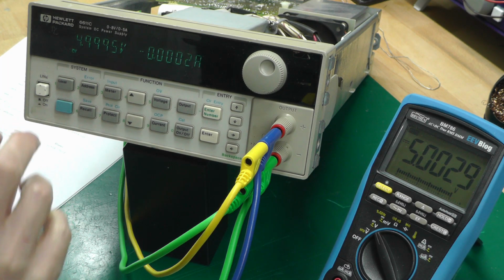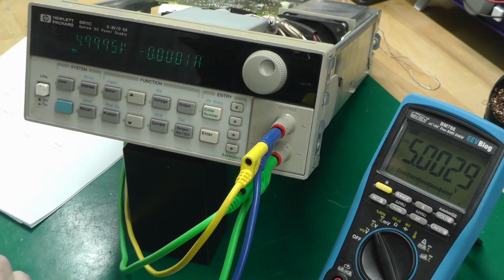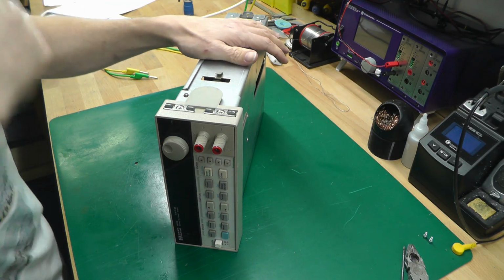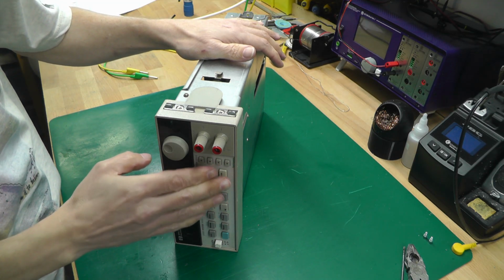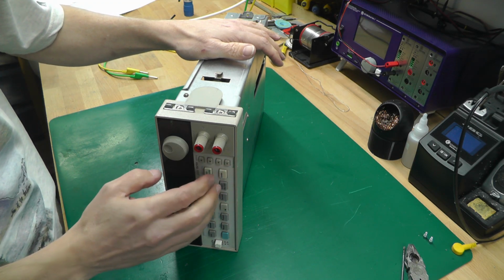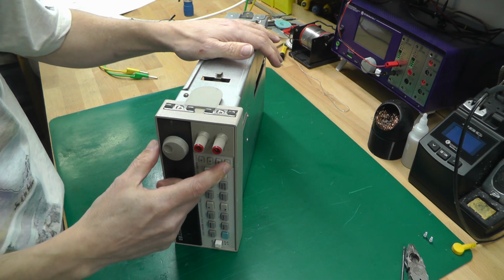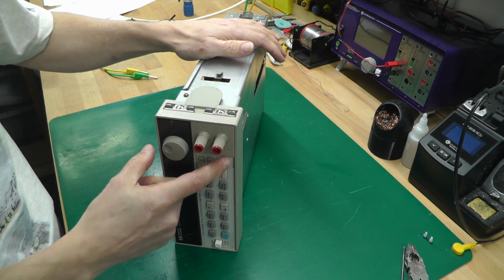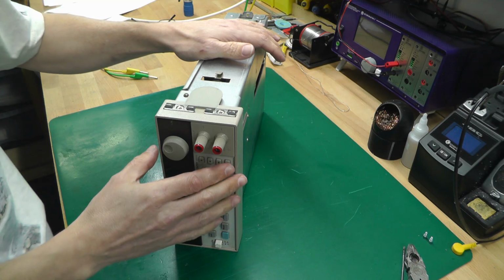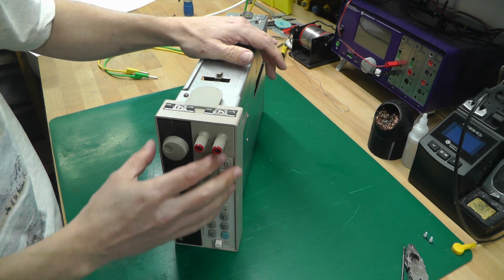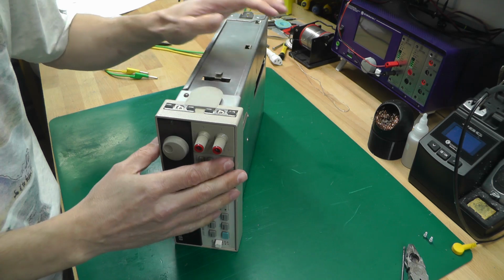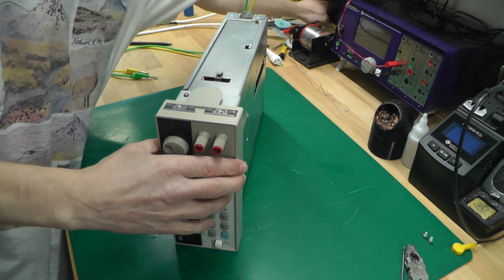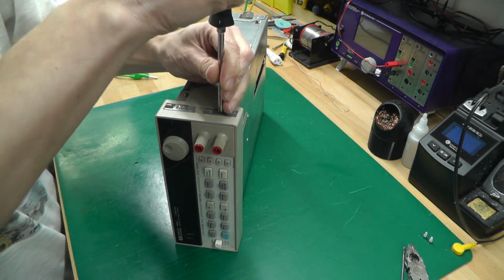So I'll box it back up now. I'll let it sit again for a while under load, and then we'll try recalibrating again with the case on. So before I put the case on to do the final calibration, I do want to look at these buttons in the front there and clean up the contacts. As remember at the beginning I noticed that this bottom button here wasn't really working too great unless you really pressed it hard. So it's probably the contacts on the membrane are needing cleaned there. So I'll do that now. So let's open it up a little bit further and see if I can take this front panel off.